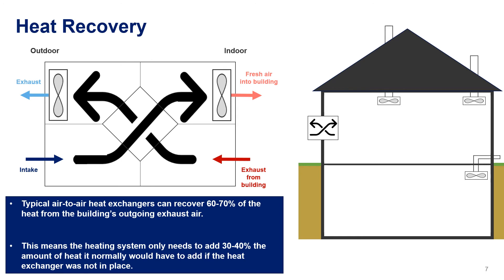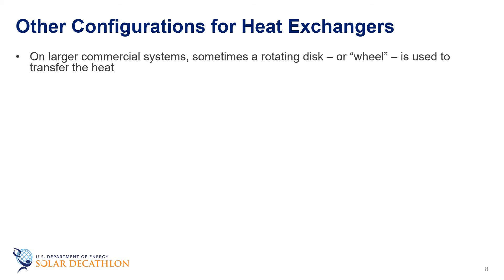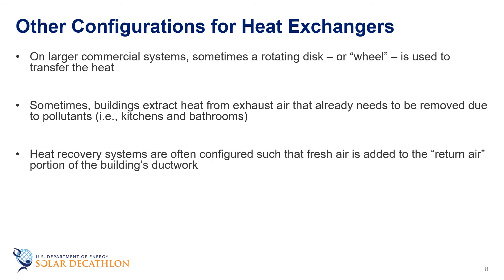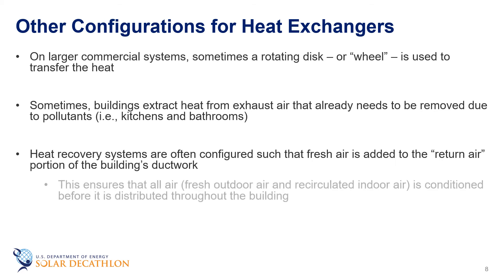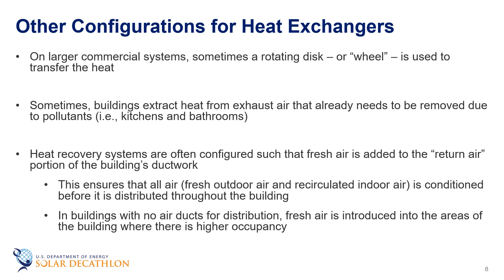The square box in the middle of the diagram is the heat exchanger. It is made up of passageways that are perpendicular to each other. Air from one passageway heats up the heat exchanger, and the heat is added to the airflow in the other passageway. Fans are used to move air through the heat exchanger, and sometimes the fans are arranged such that there is only one motor that runs both fans. This is not the only configuration of heat exchangers — sometimes a rotating disc is used to transfer the heat, especially on larger commercial systems. Sometimes air is pulled from areas of the building where there are pollutants, including kitchens and bathrooms. Fresh air is often dumped into the return of the furnace system's ductwork and is used to distribute conditioned air throughout the building. If there is no air distribution system, fresh air is introduced into areas of the building where there is higher occupancy, such as the living room and bedrooms.